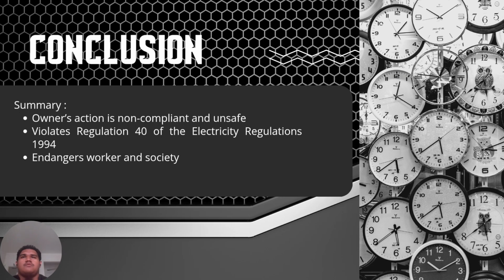To wrap up our presentation, let's review the key points. First, it is clear that the owner's decision to exclude a fire extinguisher in the electrical substation chamber is both non-compliant and unsafe. This setup violates Regulation 40 of the Electricity Regulations 1994, which mandates appropriate firefighting equipment in electrical installations.